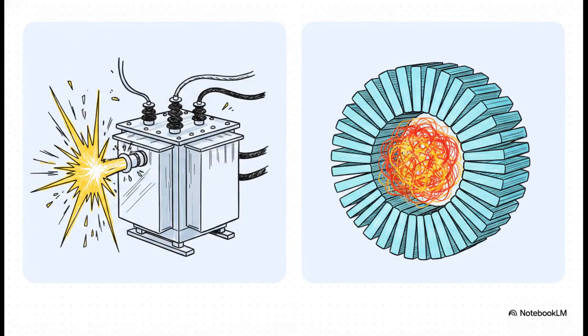To really get why, we need to compare two very different types of faults. First, think of a bushing flashover. This is essentially an external spark jumping where it definitely shouldn't on the outside connection point. It's loud, it's visually obvious, and it usually pulls a massive amount of current right away. But then, you have an interturn fault. This is a silent, hidden short circuit buried deep, deep inside the winding coil itself. Both are terrible for the transformer, obviously, but that interturn fault is way more subtle at first, which actually makes it incredibly dangerous.